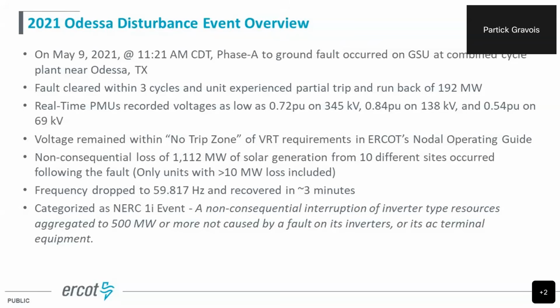The frequency dropped to about 59.82 and recovered in about 3 minutes. This was categorized as a NERC 1I event, which is a non-consequential interruption of inverter type resources aggregated to 500 megawatts or more, not caused by a fault on its own equipment. So in some cases, the fault was pretty far away. West Texas is a huge area. We had some units that were tripping off a couple hundred miles away from the fault.